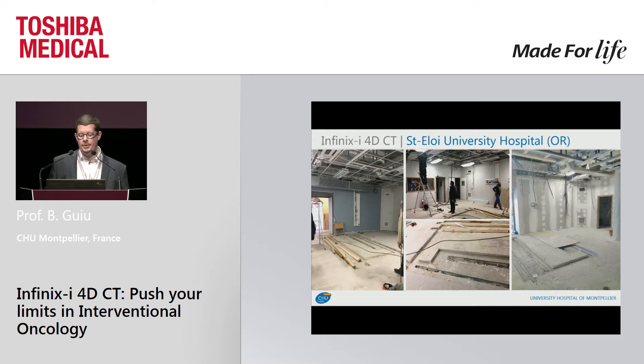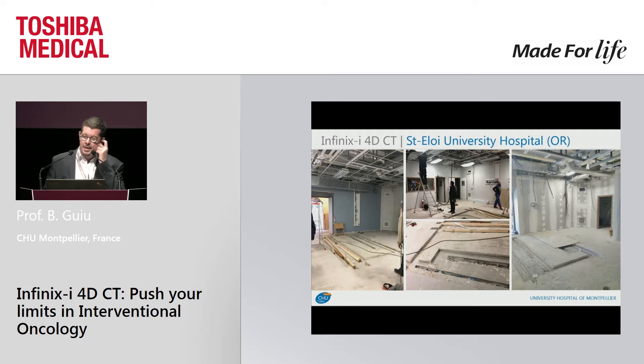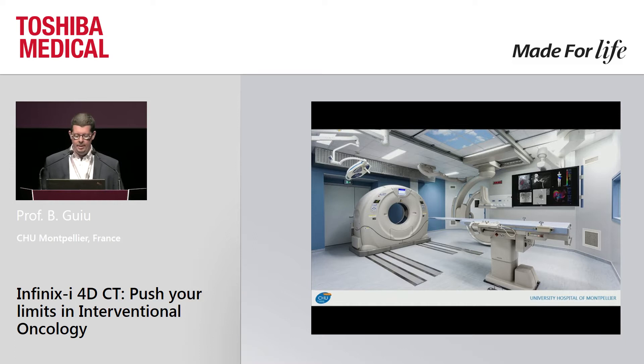We launched the construction work — a huge undertaking. Eight months were necessary to install this room. Three reasons: first, this system is more complex than a classical angio suite. Second, we are inside the operating room with surgeons working around us — if you make noise, surgeons are not happy, so you have to stop working. Third, problems with air treatment — you have to ensure no contamination of the air in other surgical rooms before starting any work, and this takes a long time. But the result is nice — this is my room.